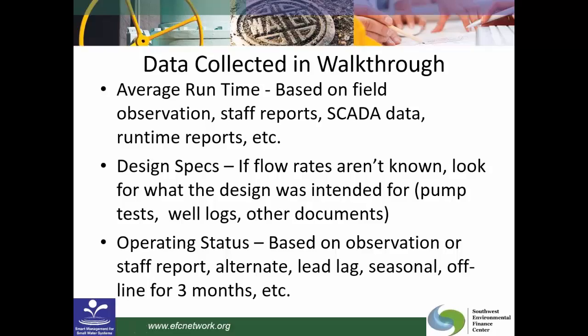And then the operating status. When you are in the field and someone says, oh, we alternate pump one and pump two, they never run at the same time, or we have three pumps and we run them lead, lag, spare, make notes of that. As you're looking at your energy costs, you can then understand maybe why one's running more than the other, and is that really what's best for your utility.